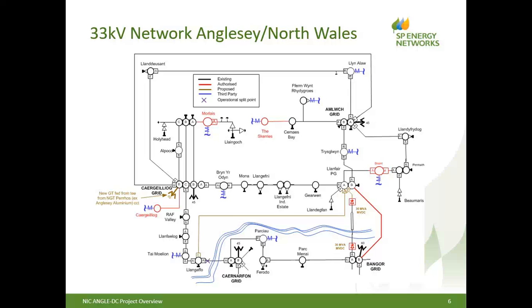Obviously, we're operating the existing circuit at DC, and we'll be operating them at plus or minus 27 DC. We're a bit unsure and a bit nervous of how this will pan out in terms of the effects on the cable, and I'll come on to that a bit later. So one of the ways we're trying to de-risk the project is by having this additional circuit, which we also need to get the DC link circuit off while the work's being undertaken and the converter stations are being connected. So that's an additional circuit that we're putting in, and that'll run very close to the existing circuit.